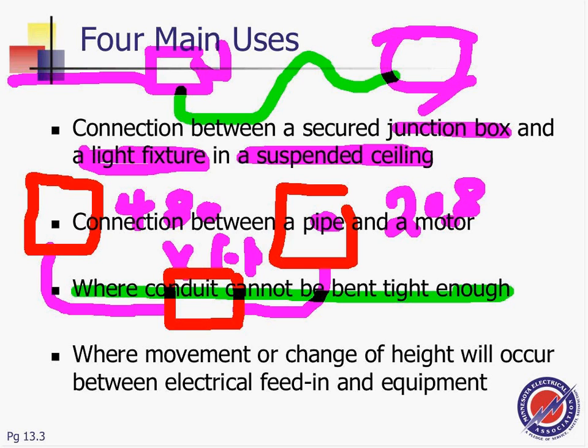And in this case, you will pull the equipment grounding conductor or bonding jumper. Remember, the flex is not meant to ground. It's not meant to be your grounding system. Okay, so you lose your grounding.